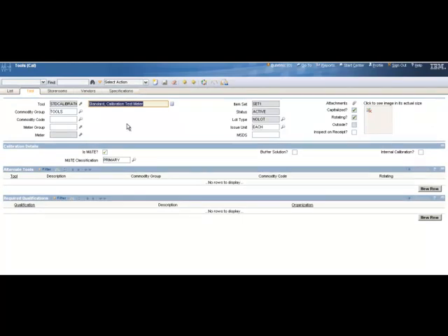The tool record basically has a tool ID. This standard value appears as a tool ID. This is actually located in the inventory table or the item master table. It basically has a different type of item, called, instead of an item like an inventory, it has a type called tool. What this does, these really are your calibration standards. It's the only time I really see these used for calibration standards. And a couple things you'll always find is the tool ID used for calibration standards will have it checked as rotating, and you'll have this button checked over here for is MTE, is measuring test equipment, and have an MTE classification, in this case primary standard.